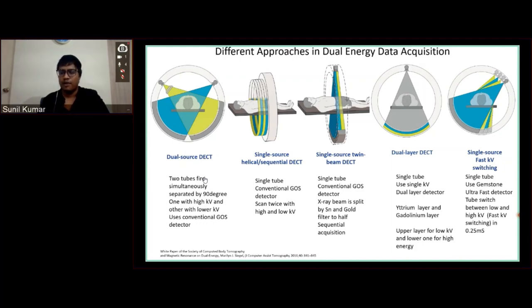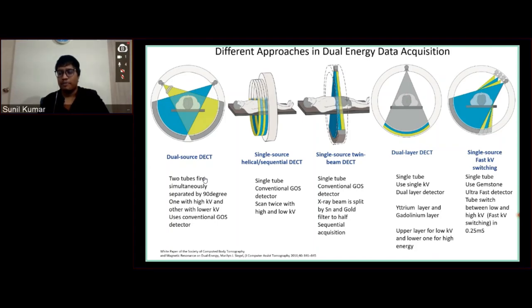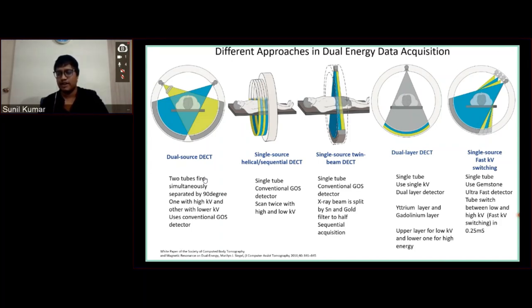Coming to the tube: the tube invariably switches quickly from one energy — say from 80 to 140 kVp — in 0.25 milliseconds. That is a very, very short duration. If you put it in perspective, one second is 1000 milliseconds, so 0.25 milliseconds is not even a blink of an eye.